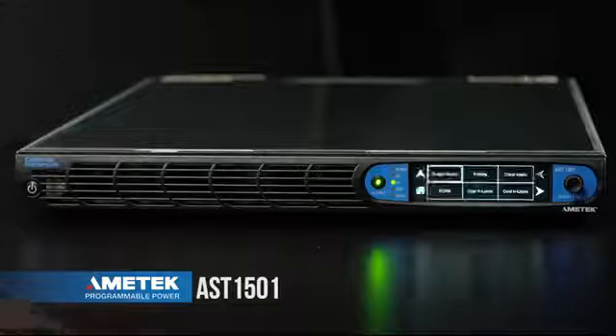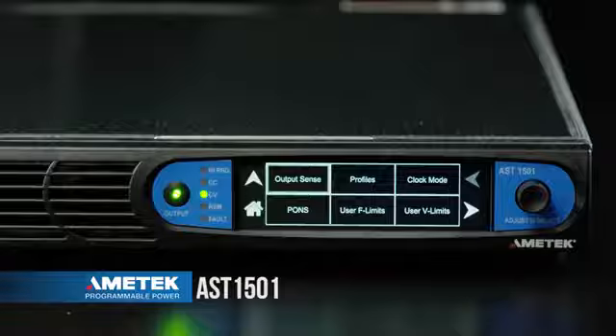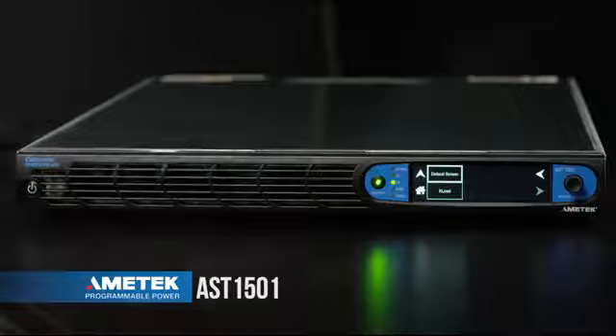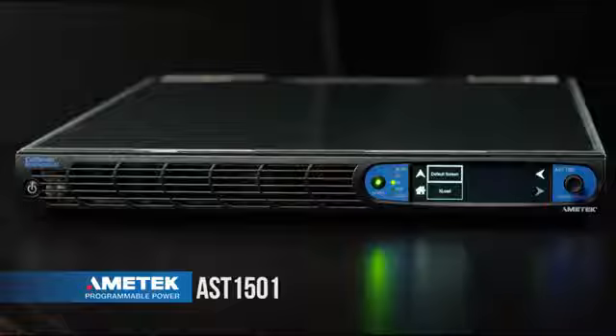Selecting the configuration menu allows us to determine whether we're going to use internal or external sense, set up user profiles, select clock mode, select the power on user settings, and select user hard limits for voltage and for frequency. Selecting the right menu allows us to set our default screen timeout and our reactive load parameter.